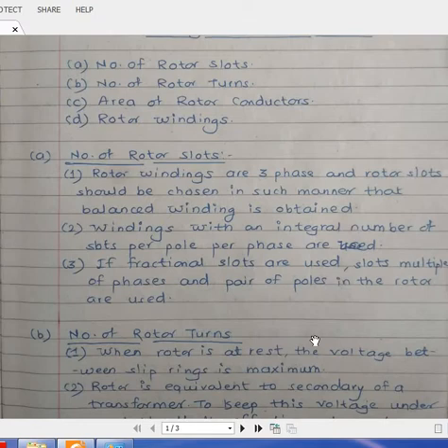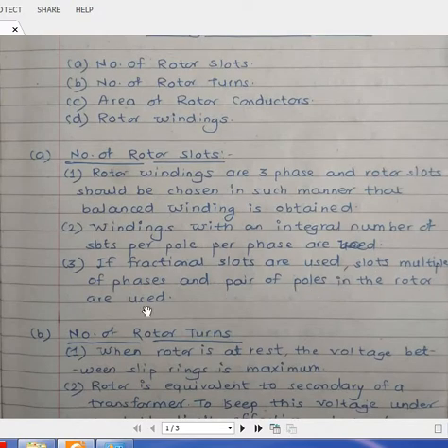The second point: you have two options when choosing slots for wound rotor induction motor. First is you can have an integral number of slots per pole per phase, or you can have fractional slots. But the important point is when you have fractional slots, your slots must be multiple of phases and pair of poles in the rotor.